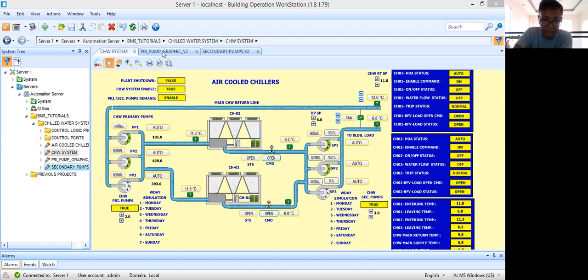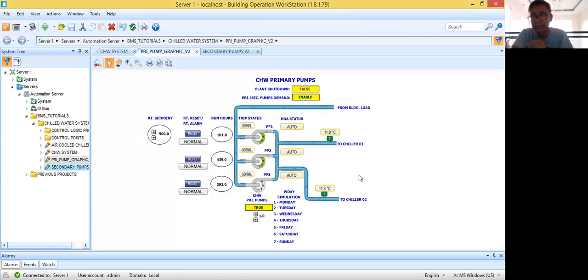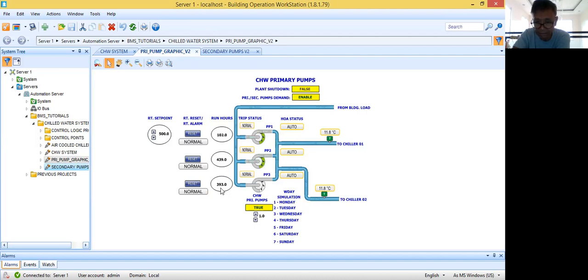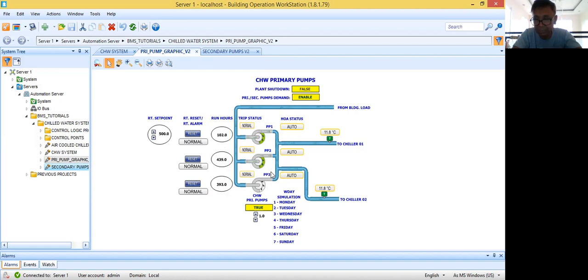I created another graphic page dedicated to primary pumps. So this is my chilled water primary pumps. I have included here a runtime setpoint — I've used a 500-hour setpoint. For the sake of simulating the operation, I'm using minutes. As you can see, my pumps are already running. Pump two is running at around 439 minutes, pump three is at 393 minutes, and pump one is at 100. The run hours are not the same for these three pumps because I'm trying to sequence them on a daily basis.